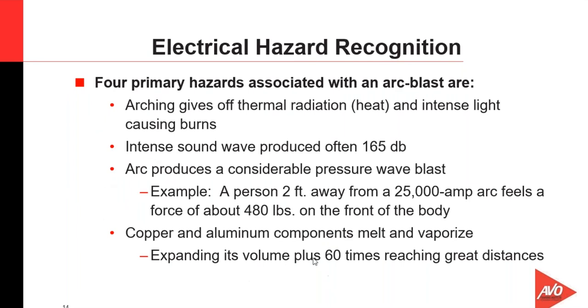The four primary hazards associated with arc flashes begin with radiation, the intense light. This is ultraviolet light given off by the arc flash during the intense arcing. There is also a sound wave produced that can exceed 165 dB. 165 dB on a sudden impact to the ears is going to create all kinds of damage to the eardrums.